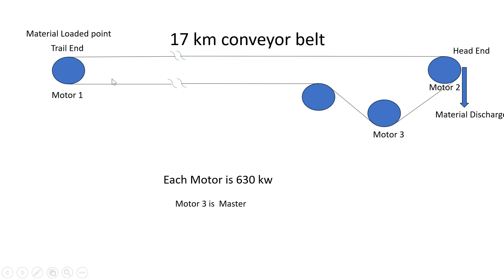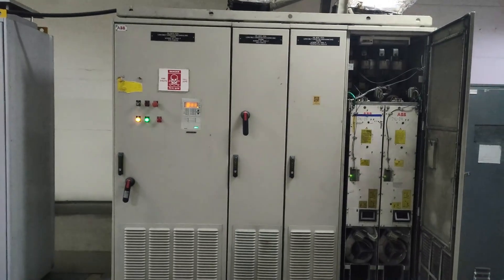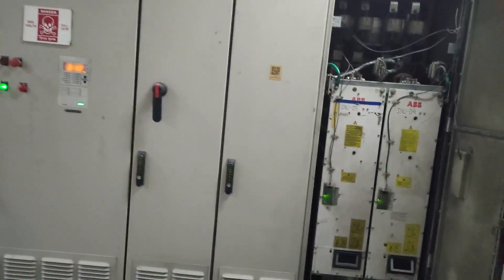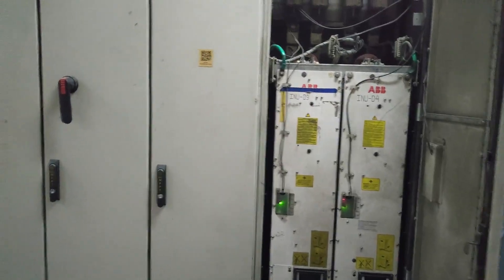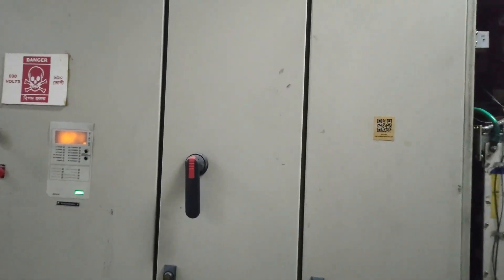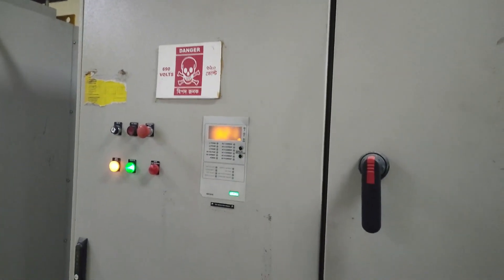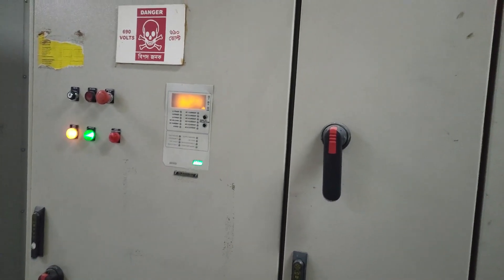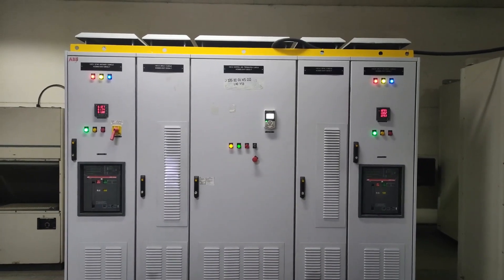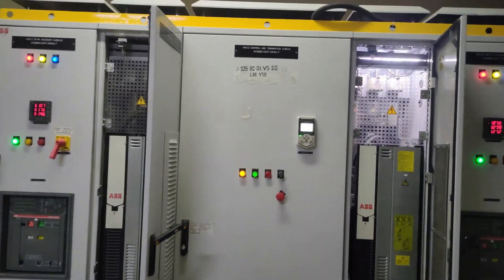Earlier, all three motors were run by the same series of drive, the ACS 800. But because of spare part availability, we replaced the Motor 2 drive with an ACS 880. So we have two old ACS 800 drives running Motor 1 and Motor 3, and the new ACS 880 drive running Motor 2. ABB engineering commissioned it last year and it was running fine. Recently we started facing the issue of Motor 1 and Motor 3 taking more current.